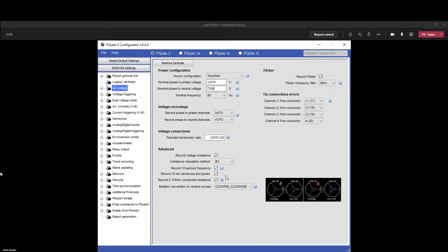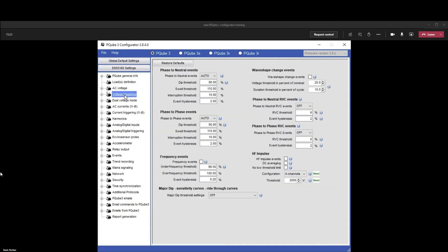Phase rotation here on the west coast is counterclockwise. It varies, so you should know which phase rotation yours is, but let's leave it all as default. For voltage triggering, I recommend for the first time you set up a PQube, you actually turn all these off.